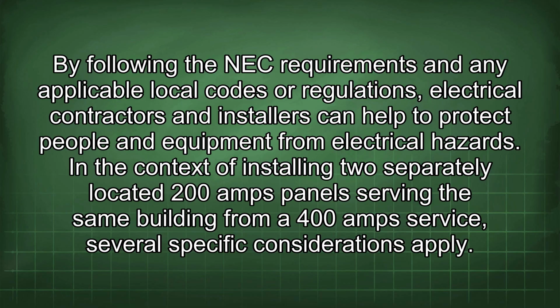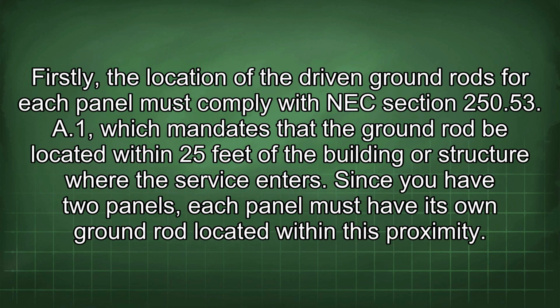In the context of installing two separately located 200 amp panels serving the same building from a 400 amp service, several specific considerations apply. Firstly, the location of the driven ground rods for each panel must comply with NEC section 250.53(A)(1), which mandates that the ground rod be located within 25 feet of the building or structure where the service enters. Since you have two panels, each panel must have its own ground rod located within this proximity.